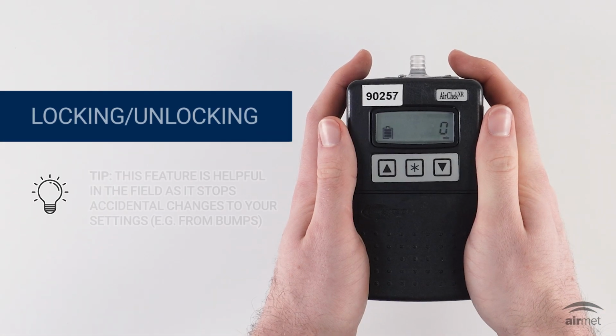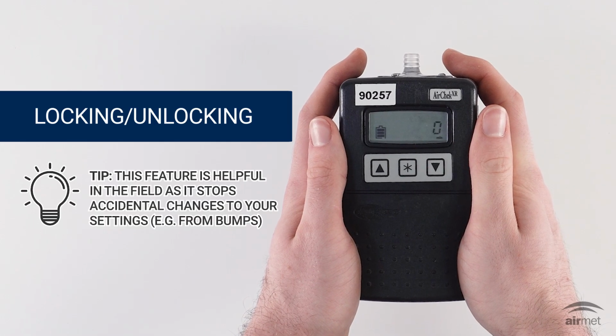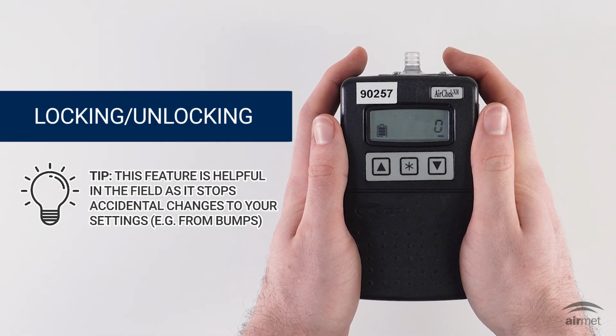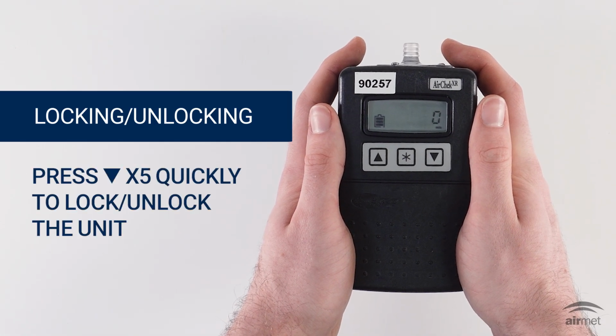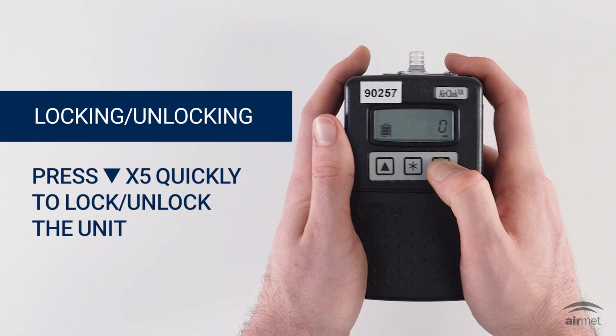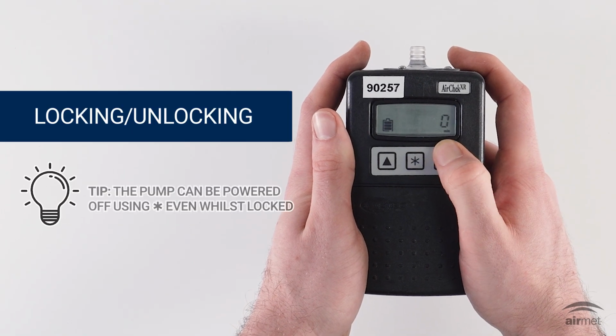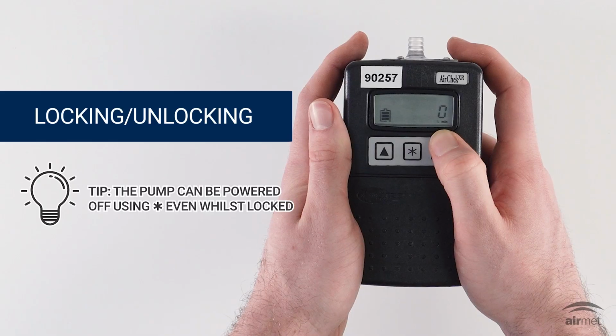The lock and unlock feature is really useful in the field, as it stops any accidental changes to your settings. To lock or unlock your pump, press the down arrow 5 times quickly. When the unit is locked, a flashing L appears on the screen.